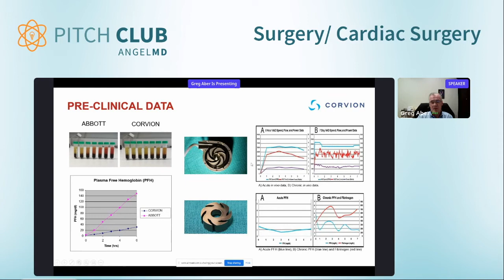We then went on to animal trials, which we're currently in the middle of. The pictures in the middle here are of the pump directly out of our first chronic animal study. No thrombus, no deposits, perfectly clean pump. Our free hemoglobin levels stayed at normal, as if there was no pump in the animal at all, at around 1 to 2 milligrams per deciliter. Power was 1.5 watts and flow was 4 to 6 liters a minute. So pretty remarkable. This type of data has never been seen for an LVAD.